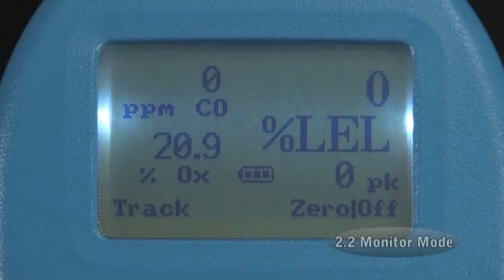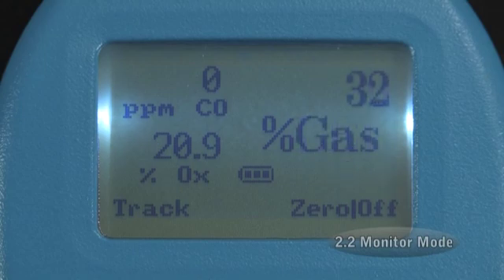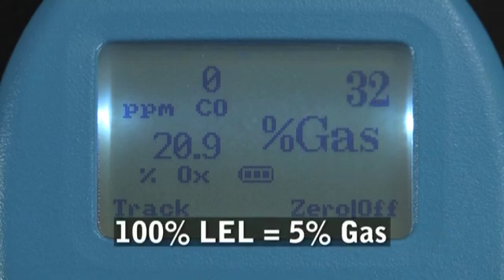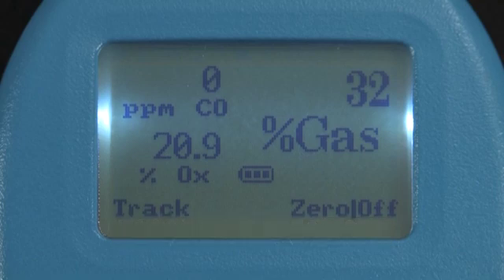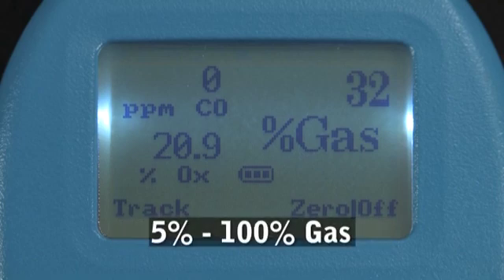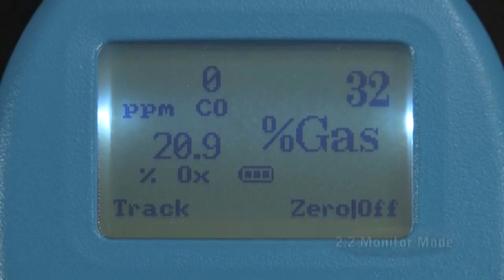If your company uses percent LEL, the Explorer will automatically switch from percent LEL to percent gas at 100% LEL, that is, at 5% gas. The Explorer will display from 5% up to 100% on the percent gas scale. The Explorer always displays the scale it is using, either percent gas or percent LEL.